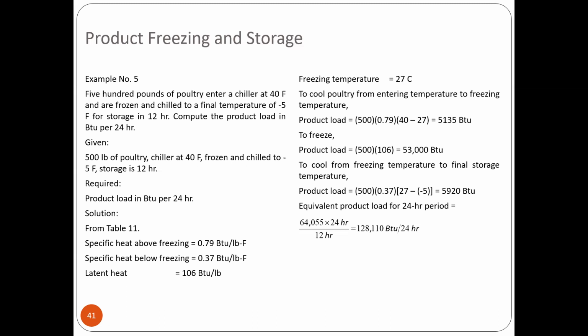Therefore, the equivalent product load for 24 hours is, i-add mo to, 5135 plus 53,000 plus 5920 is 64,055 times 24 over 12 is 128,110 BTU per 24 hours. So, ito yung equipment load mo.